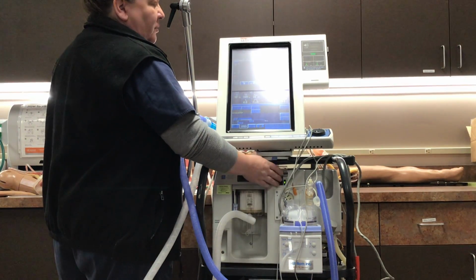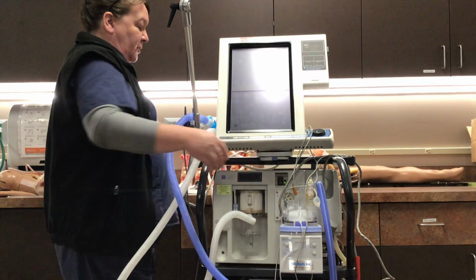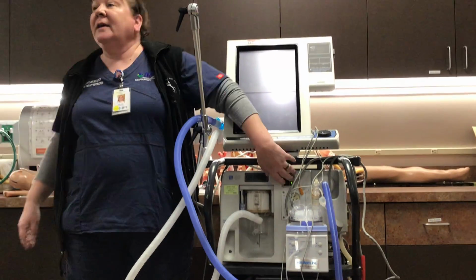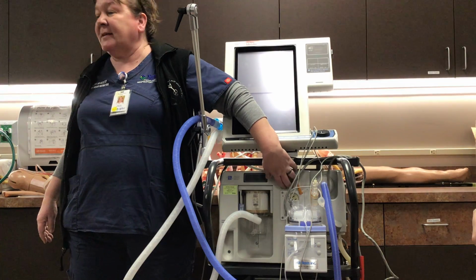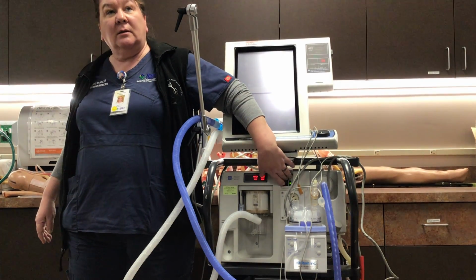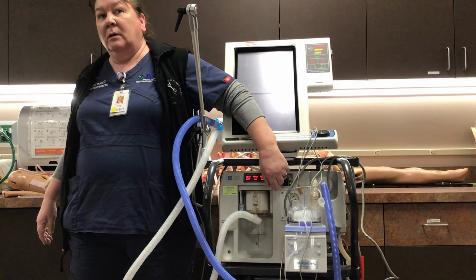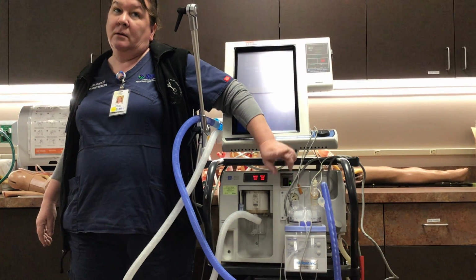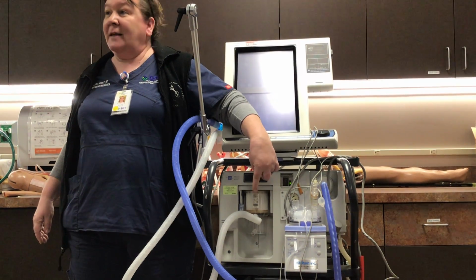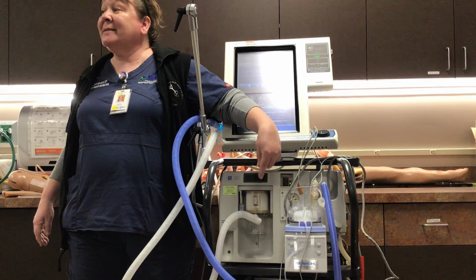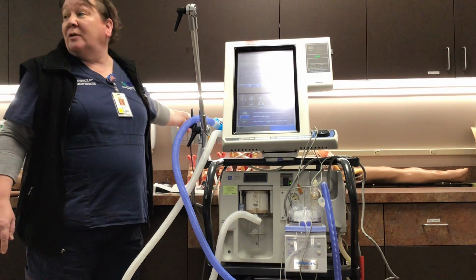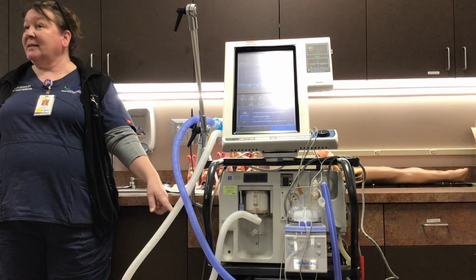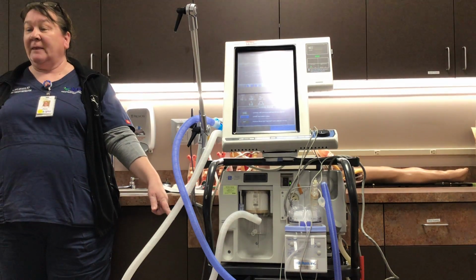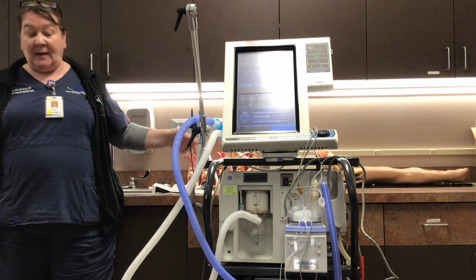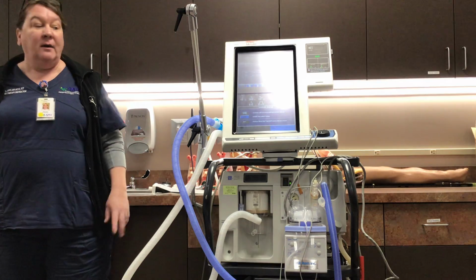Okay, so when you first turn this ventilator on, I'm gonna just do this real quick. You're gonna hear the air compressor come on because it's part of the testing. So we're gonna turn it on. That's the air compressor. So it's running its test. I'm currently hooked up to air. So it's just testing that it's working and then it shuts it down because it says I'm already hooked up to 50 PSI. I don't need my air compressor to run.